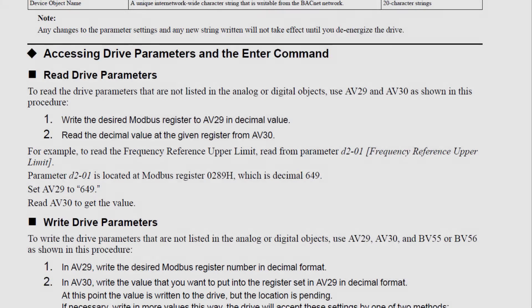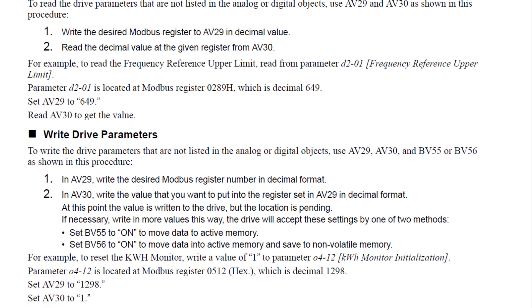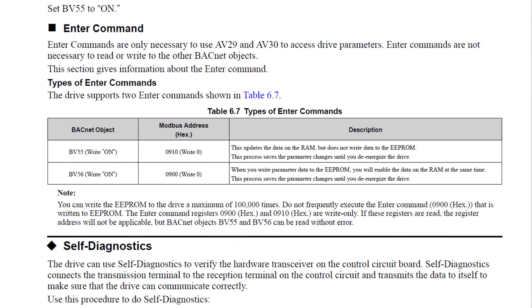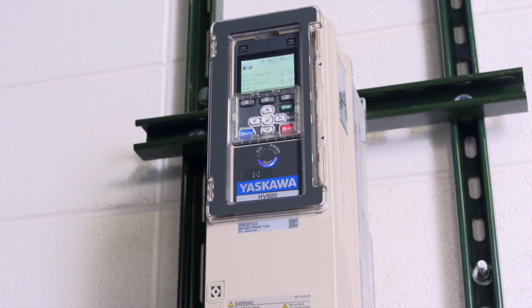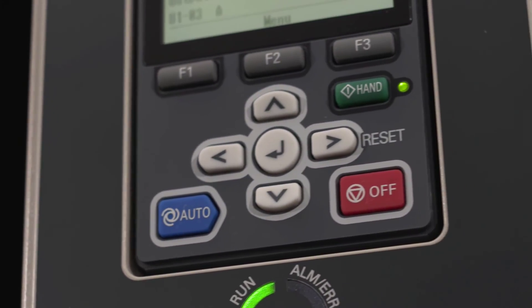If you are interested in accessing drive parameters that are not listed in the standard object groups, you can use AV29, AV30, and BV55 to read and write drive parameters. The knowledge learned here will give you a firm grasp on BACnet when applied to Yaskawa products.